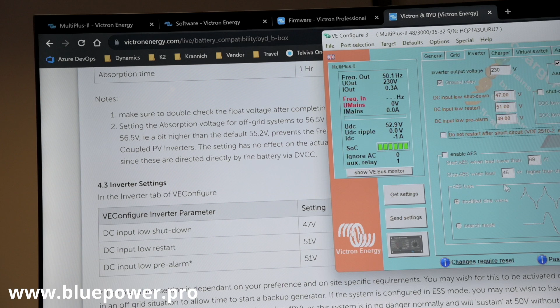The next tab is our charger. Here on top, we can activate or deactivate the built-in charger of the inverter. Then we've got weak AC input. South Africa does have weak AC, so I always activate that. What that does is it gives a little bit more slack on the input parameters from the system. So if you've got a system in the boondocks, in the middle of nowhere, on a very bad line, and the voltage fluctuates, in the morning it's at 250, but in the middle of the day it's at 200 volts, then your inverter isn't going to want to charge your batteries with those voltage fluctuations. So then it's required to enable the weak AC input. Otherwise it's only going to bypass the power, never charge your batteries from your mains.